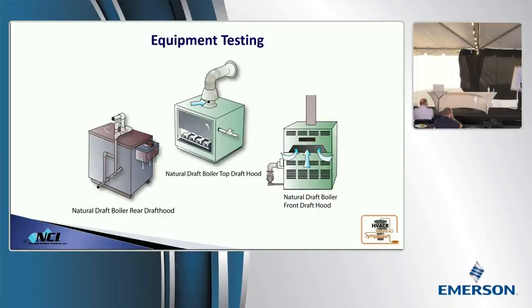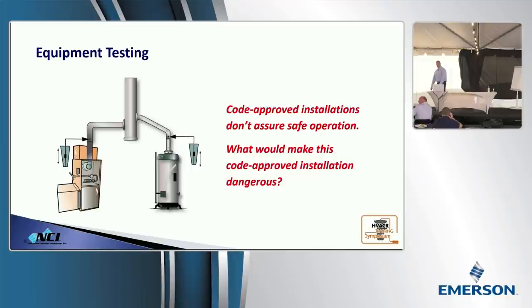So if it's a boiler, regardless of where the draft hood is, you're going to measure your combustion readings before the draft hood. If you can gain access to each individual heat exchanger outlet, measure it. If you can only get underneath the hood, you need one reading. And what you're looking for is the area of the highest CO number. Now, as you take your readings, it's important to keep in mind that just because you got a code-approved installation, that doesn't mean it's safe. Code says something has to be there. It doesn't say it has to work. What makes this installation dangerous?